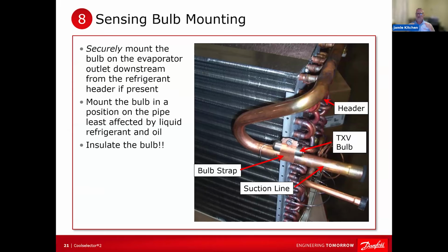If you want to increase the amount of superheat that you have for destabilizing the TXV, if you want it to happen at 5 degrees instead of 3, just loosen that bulb up a little bit, and it will become unstable a lot quicker than it does if it's properly mounted and insulated.